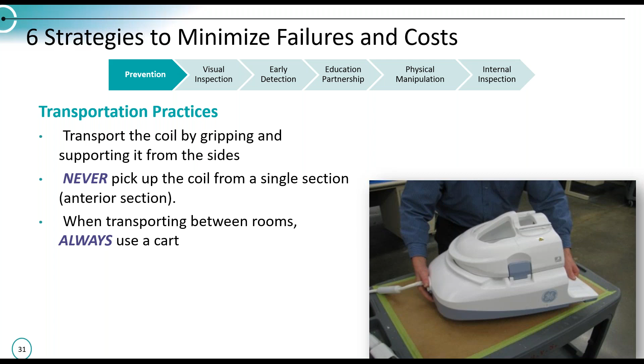Flex coils should always be cradled either from the bottom or gripped at that large center solid housing. Some of the coils actually have a sticker and a label on it to remind the users not to pull, not to lift by those flexible sections. Again, underneath that coil section, that foam section, are flexible circuitries, and there are discrete as well as surface mounted components embedded in that foam. And also, it should be known that you don't carry any type of medical device by the cable, let alone MRI coils.